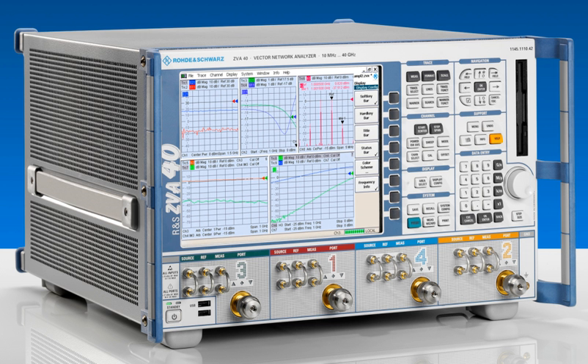Topic: calibration or error correction. A network analyzer, like most electronic instruments, requires periodic calibration. Typically, this is performed once per year and is performed by the manufacturer or by a third party in a calibration laboratory. When the instrument is calibrated, it will usually have a sticker fixed to the outside, stating the date it was calibrated and when the next calibration is due. A calibration certificate will be issued.